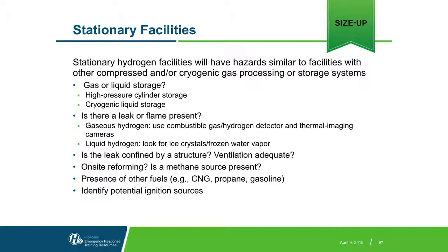This is sort of the same process as for other stationary facilities. Is there a leak or a flame present? So a gas sensor can be employed as well as the thermal imaging camera. There's no on-site reforming. Presence of other fuels is something to keep in mind because I understand that there are a lot of other fuels that are used and moved around on site. So identifying potential ignition sources is also something to consider when responding to this.